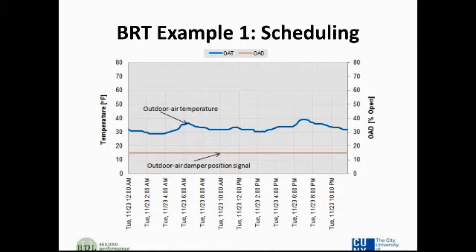So obviously it's cold out, and we don't want it to be that cold inside. We would rather not bring a lot of that air in when we don't have to. Of course, we need to bring fresh air in order to ventilate. People need to breathe 15 cubic feet per minute per person, typically, or something comparable. Maybe it's just a number of air changes per hour, or there are different ways of ventilating properly. But what you can see here is that the outdoor air damper position signal is showing that it's open about 15% for the entire 24-hour period.